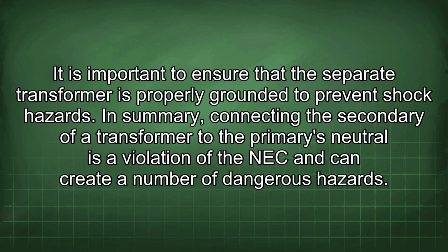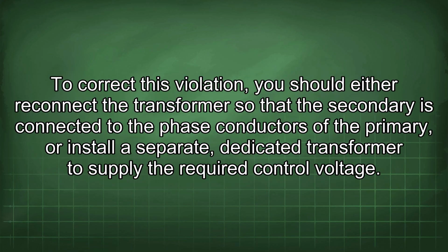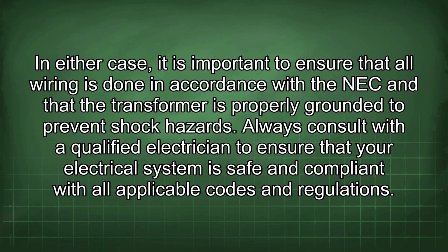In summary, connecting the secondary of a transformer to the primary's neutral is a violation of the NEC and can create a number of dangerous hazards. To correct this violation, you should either reconnect the transformer so that the secondary is connected to the phase conductors of the primary, or install a separate, dedicated transformer to supply the required control voltage. In either case, it is important to ensure that all wiring is done in accordance with the NEC and that the transformer is properly grounded to prevent shock hazards. Always consult with a qualified electrician to ensure that your electrical system is safe and compliant with all applicable codes and regulations.